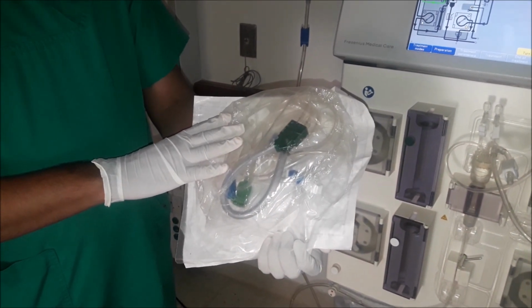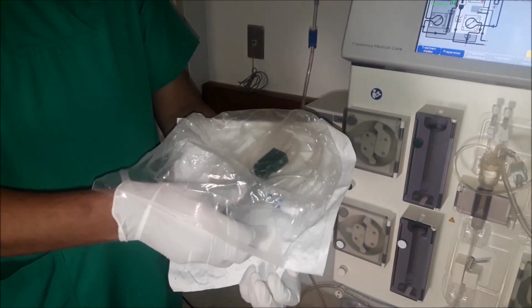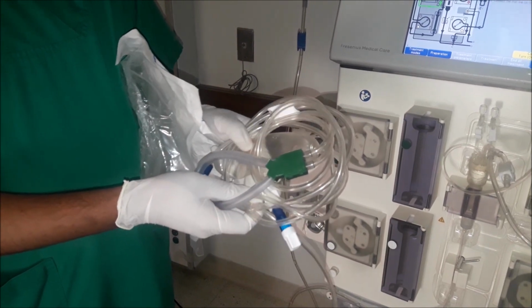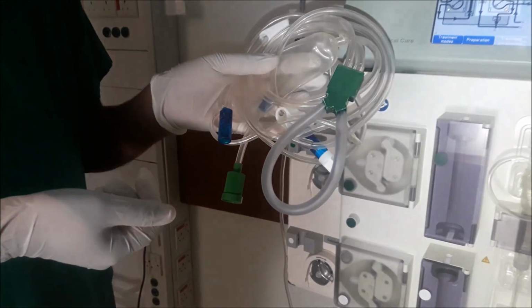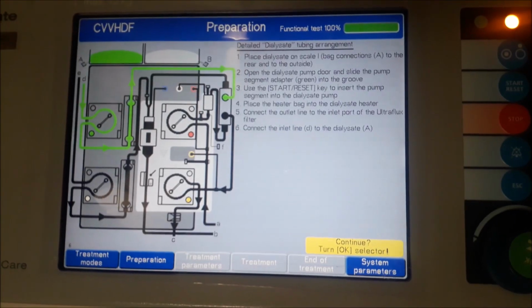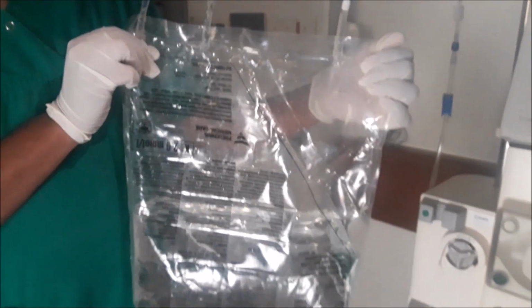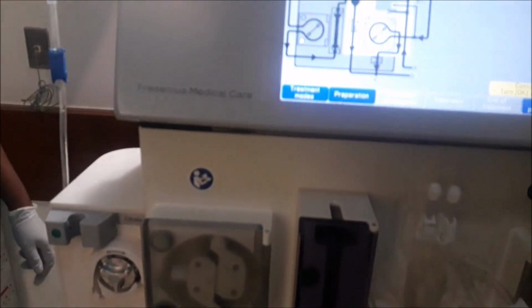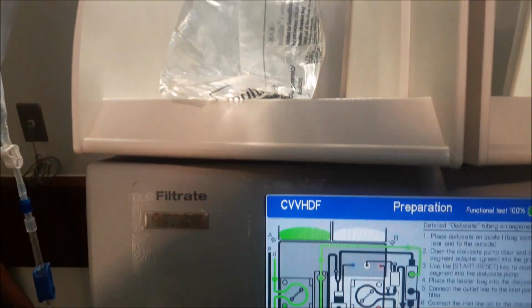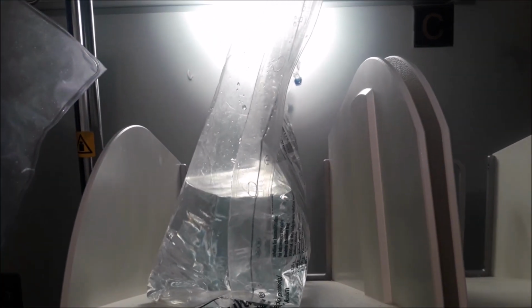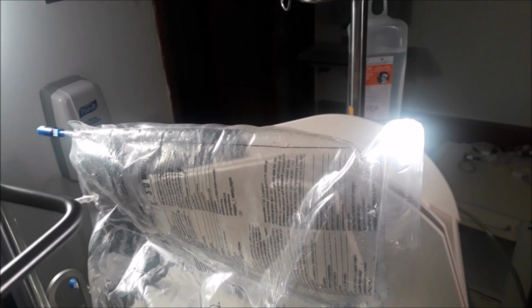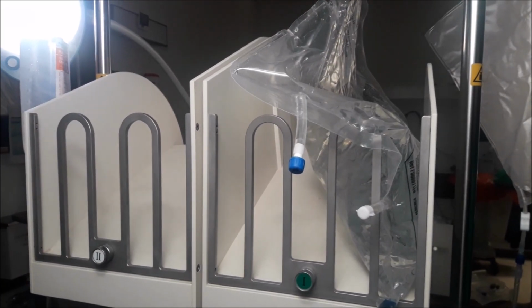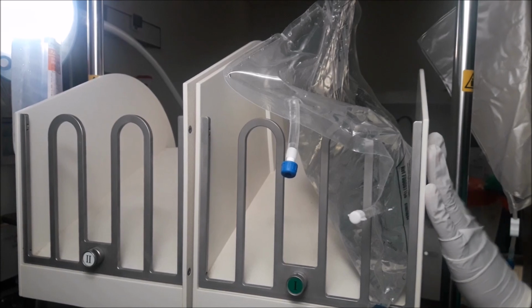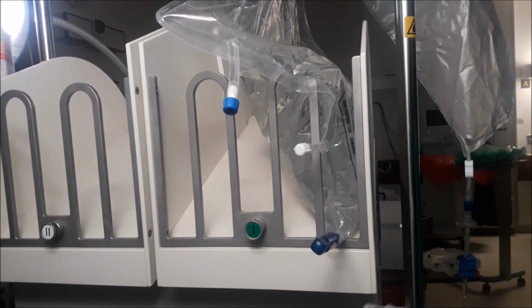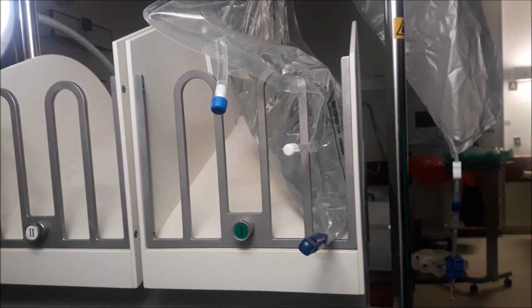This is the dialysate tubing pack. Let's open the pack and remove the tubing. Dialysate tubing is also color coded and the color of this tubing is green. Let's start the dialysate tubing arrangement. First point is place dialysate on scale. This is the back side of the machine. Here you can see we place the dialysate fluid on the dialysate scale and the outlets of the bags on the back side of the machine.